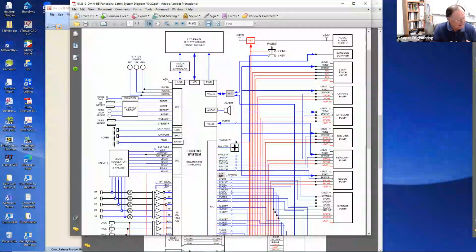When I say dialysis machine, you might think of something where people go three times a week and get dialysis. This is not that type of dialysis machine. This is used in ICUs, and it's mainly used on people who have congestive heart failure. They come in in cardiac instability, with 20 to 40 liters of fluid overload in their body that they've just retained, and they're going into multiple organ failure, their kidneys are failing. This machine is connected to them, pulls their blood out, performs the dialysis type functions, removes metabolic waste, does acid-base balance and electrolyte balance, and removes all that fluid. And you only have maybe 6 liters of blood in your body. So this thing's processing all that, and what it slowly does is remove all that excess fluid in your body.